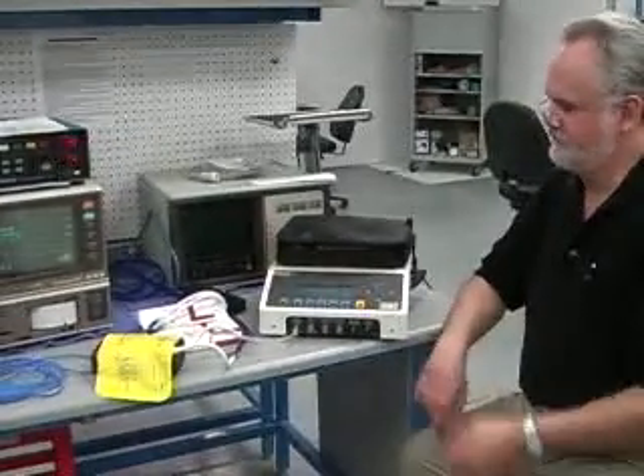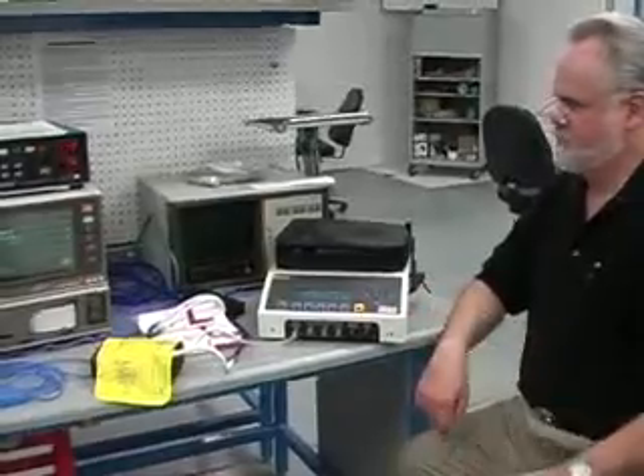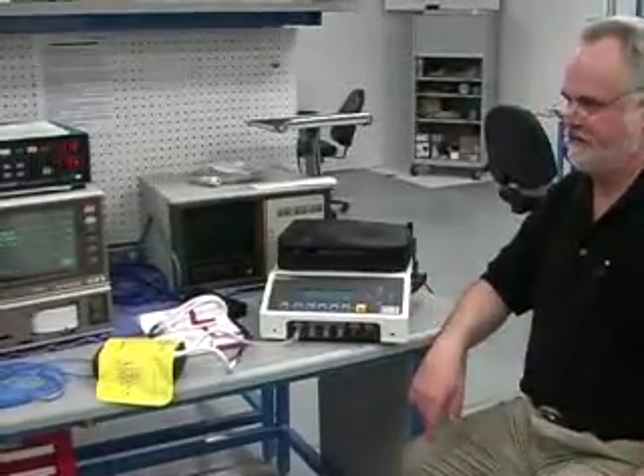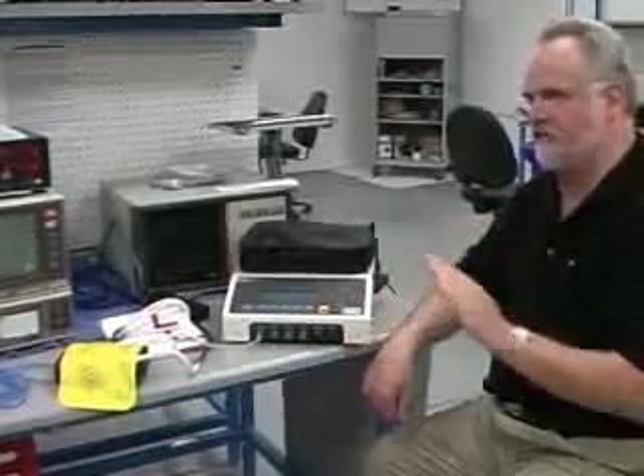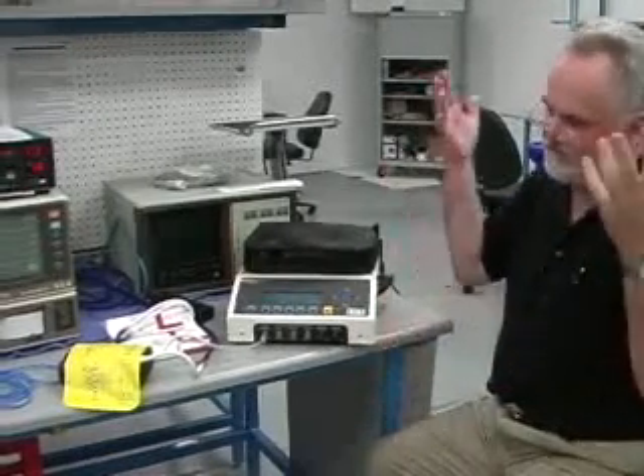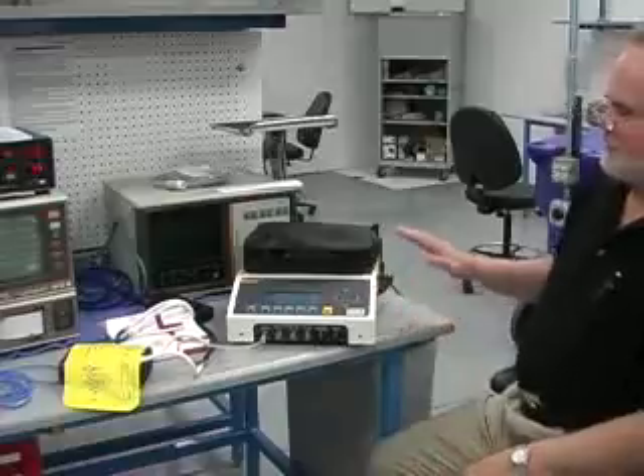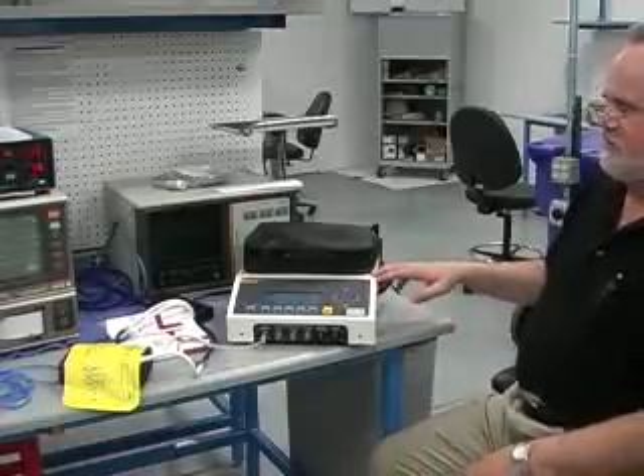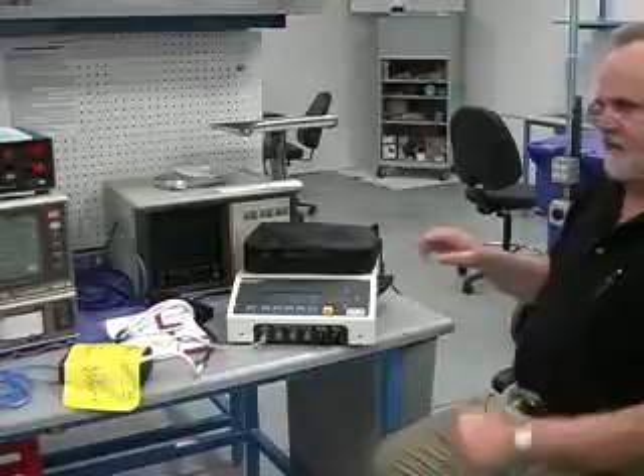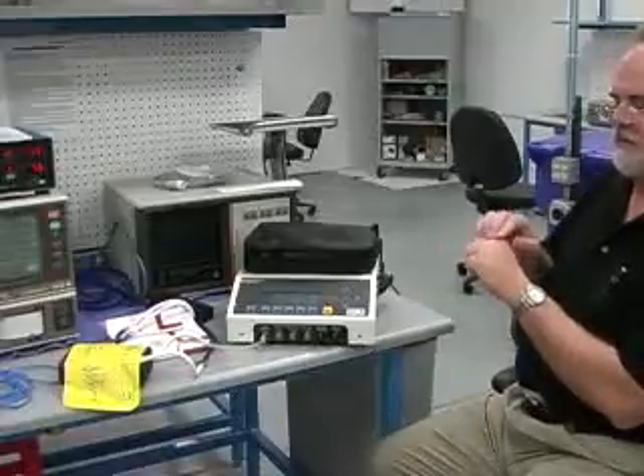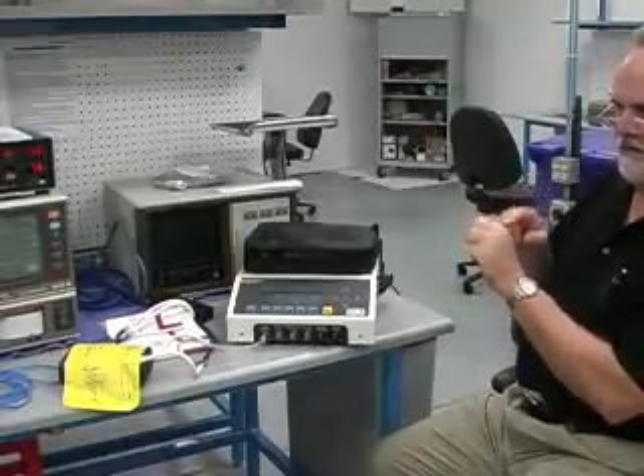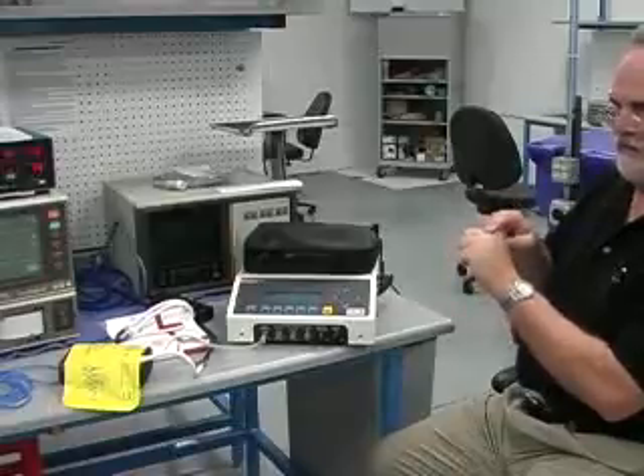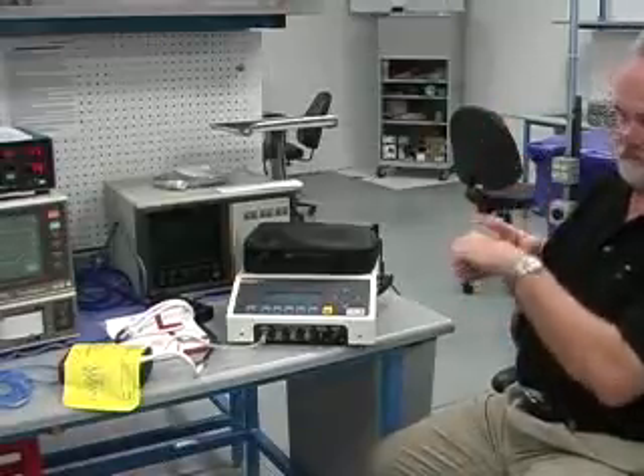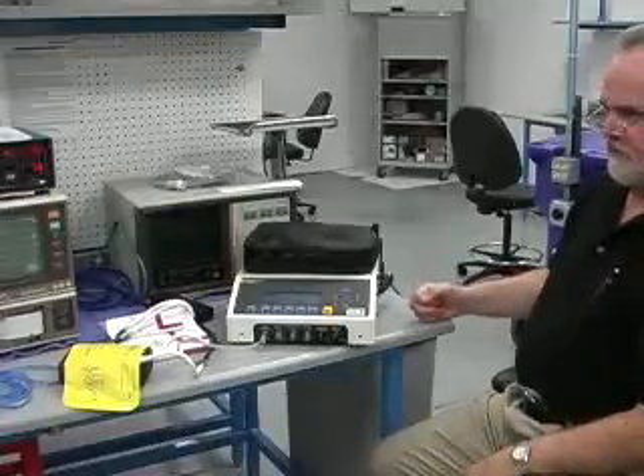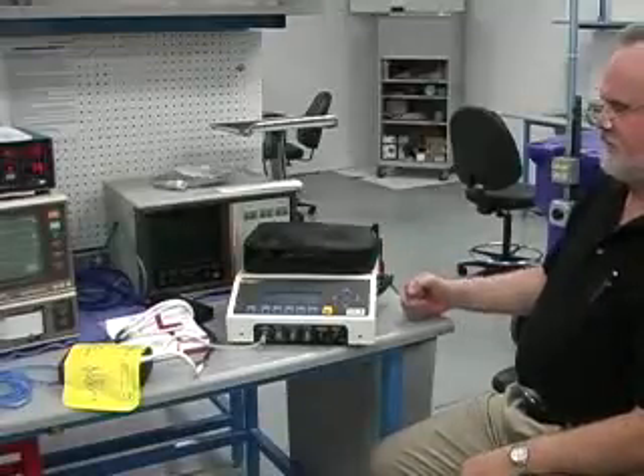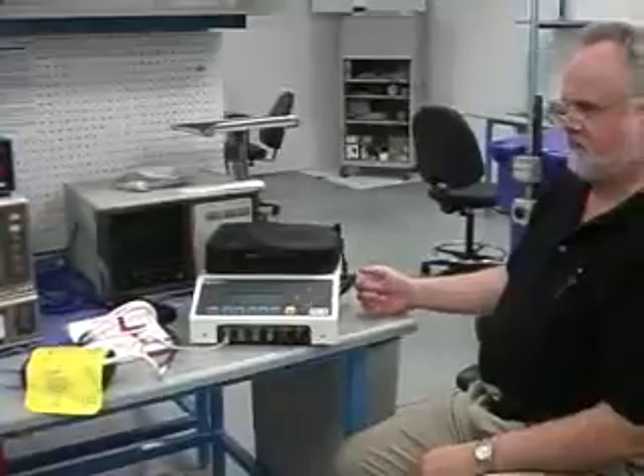Also, with some other technologies, CAS is another company, instead of measuring on the deflate, they measure on the inflation. But hey, we're still good, because with our system we measure the pressure in the cuff and output the pulse that's proportional to what the patient's doing at that cuff pressure. It doesn't matter if it's going up or going down, we generate it. So again, a very good test tool for non-invasive blood pressure.